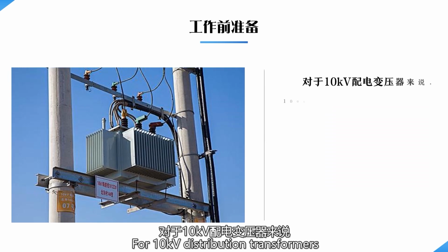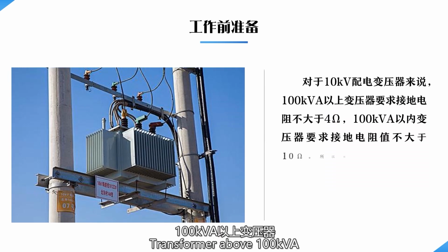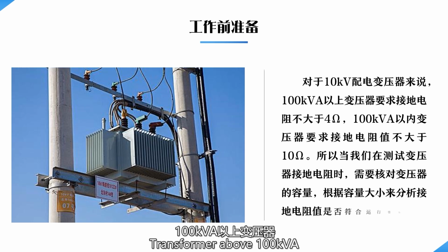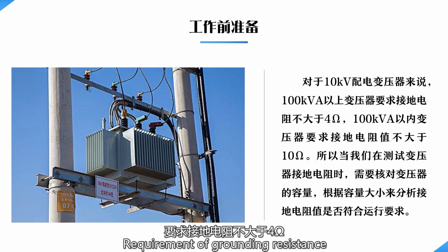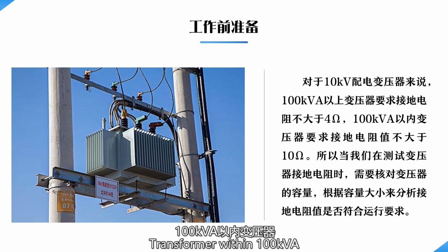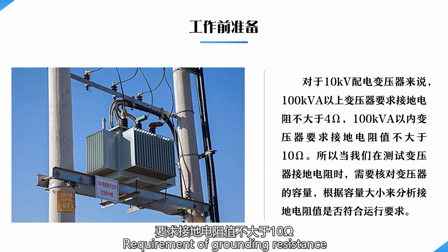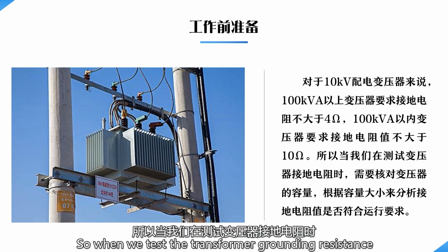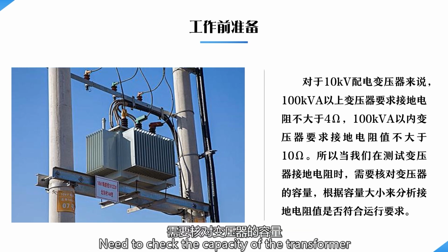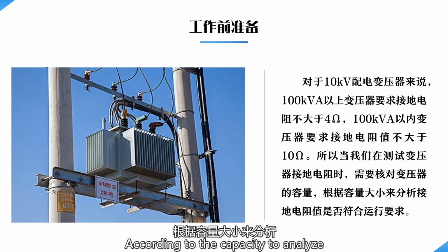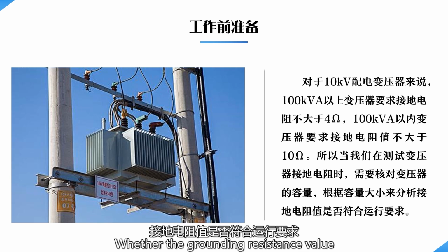For 10 kV distribution transformers above 100 kVA, the grounding resistance required is not more than 4 ohms. For transformers within 100 kVA, the required grounding resistance value is not more than 10 ohms. So when we test the transformer grounding resistance, we need to check the capacity of the transformer, and according to the capacity analyze whether the grounding resistance value meets the operational requirements.